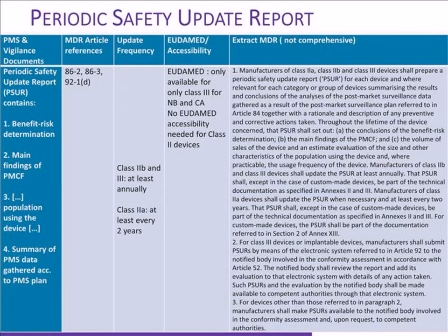If you read the text on the right-hand side, or better even go to the directive itself, since the text here is just an extract, you will see that there's a vast overlap in the content of this PSUR with the benefit risk reports, with the findings of the post-market clinical follow-up, with the summary of the post-market plan, and this certainly is one of the complexities of all this setup. This PSUR will have to be uploaded into EUDAMED by the notified body for class 3 and 2B.